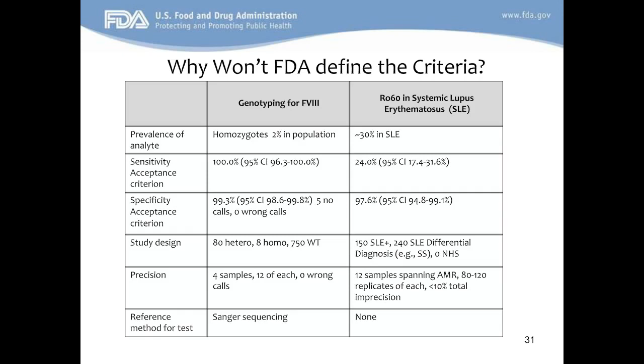Some of the surprisingly common mistakes that we see when people make submissions for in vitro diagnostics: we talked about acceptance criteria. Sometimes manufacturers will set acceptance criteria, and then when the data are analyzed, they don't meet them. This is obviously a problem because data that don't meet the acceptance criteria cannot be used to verify or validate performance of a device. Another important one is not performing the analytical and clinical validation on the final device. Sometimes manufacturers will change the device after they've done their data collection and data analysis. The performance data that we receive has to be done on the final device that would ultimately be cleared for approval.